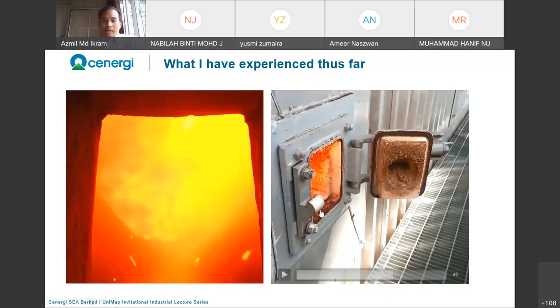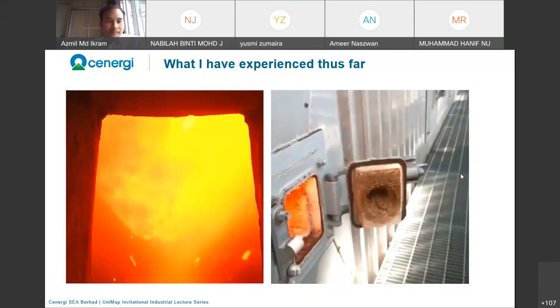For there to be fire going out, basically it's at positive pressure. Positive pressure is not good. It indicates that there must be some blockage inside in some places. So that's one of my jobs. By understanding the concepts of thermodynamics and mechanical process flows, you can understand the characteristics of this. Air is supposed to be coming into this peephole. Instead, flame goes out, so something is wrong somewhere. That's one of my jobs.